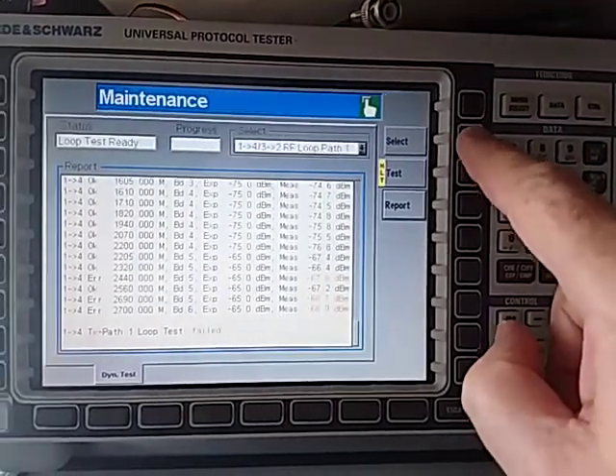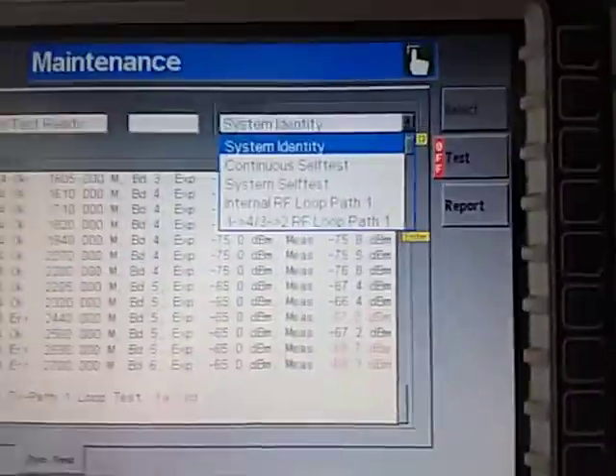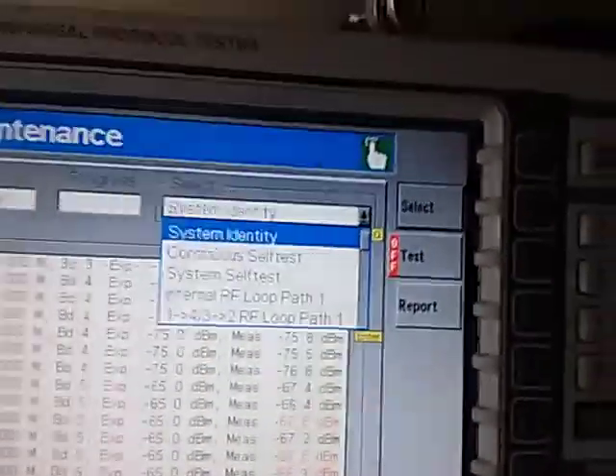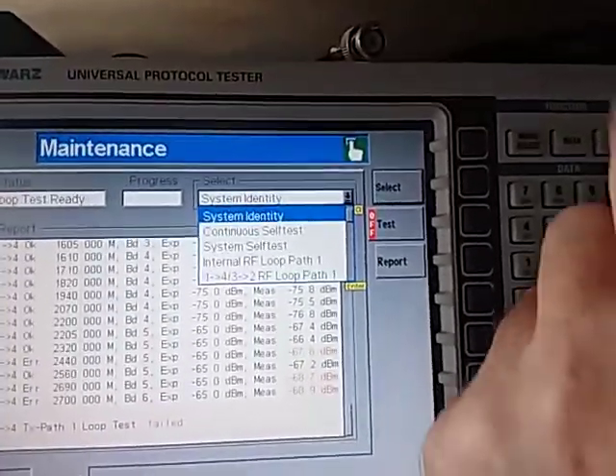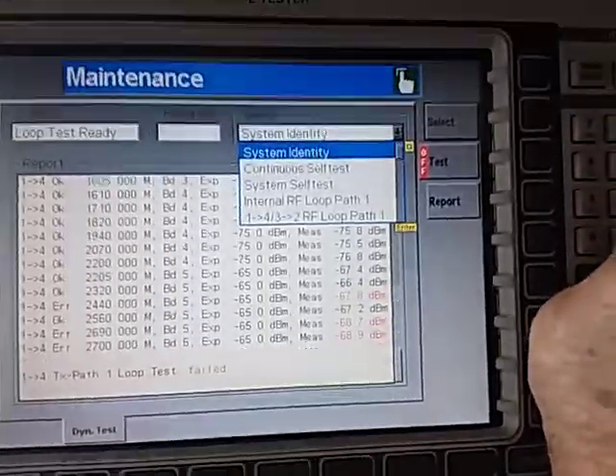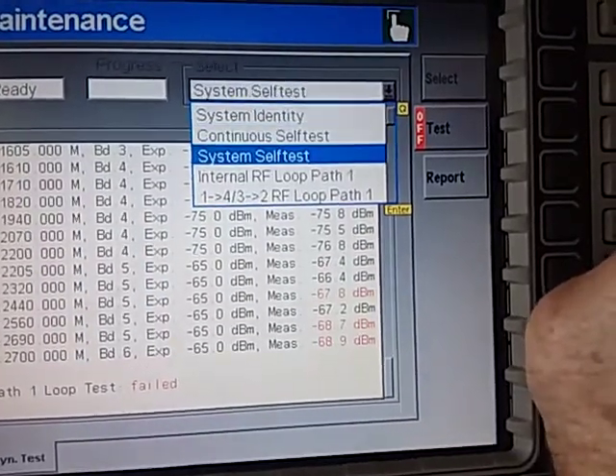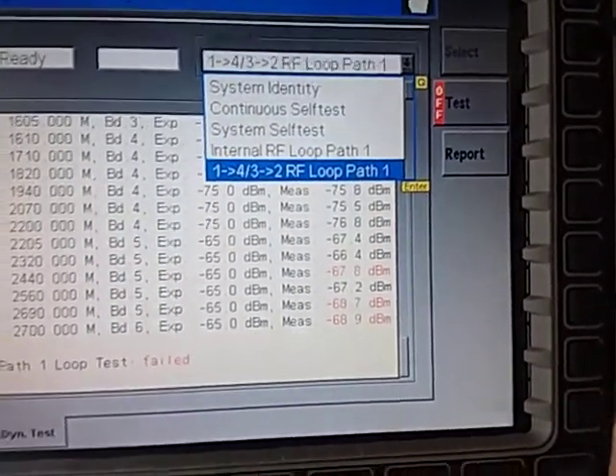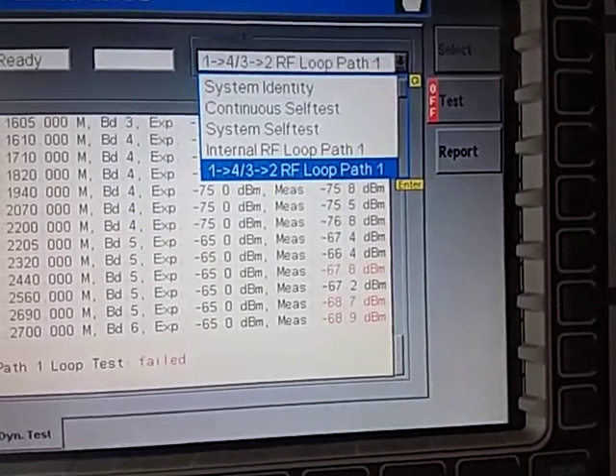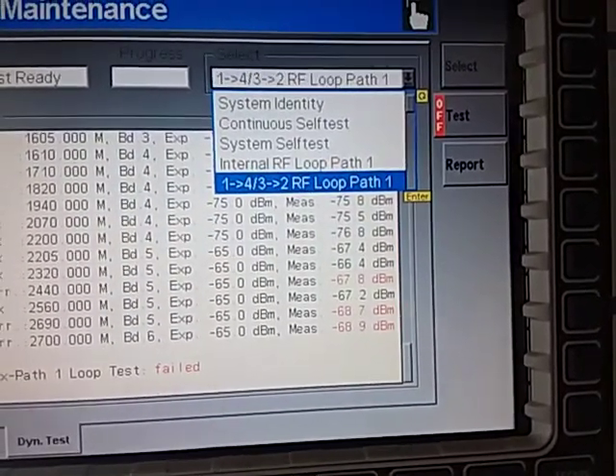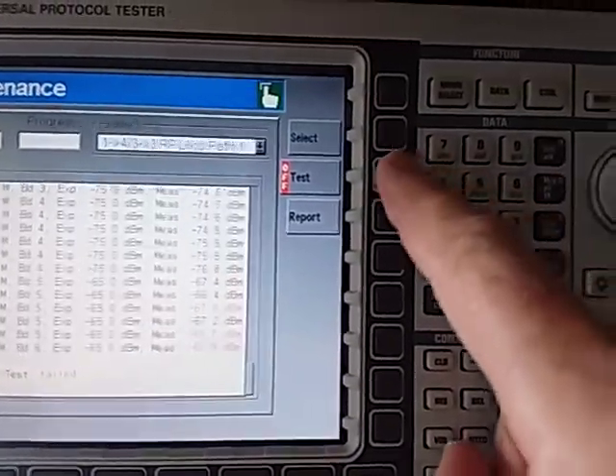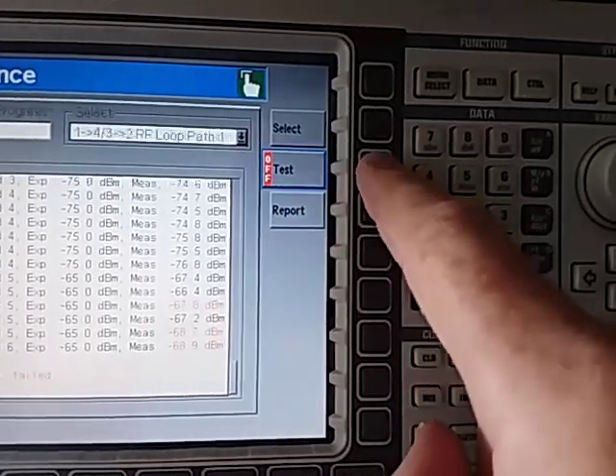We're in the maintenance screen. If you hit select you'll see there's quite a few drop downs here. This is where all the self tests are done. The main self test, or the main one that I look at to check that the input output ports are correct, is the loopback test.